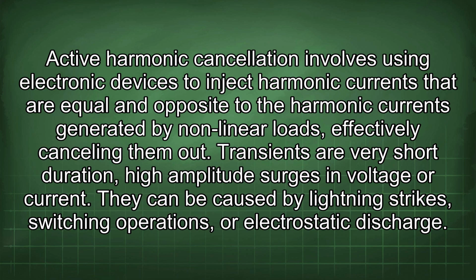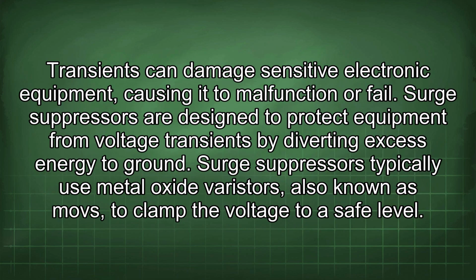Transients are very short duration, high amplitude surges in voltage or current. They can be caused by lightning strikes, switching operations, or electrostatic discharge. Transients can damage sensitive electronic equipment, causing it to malfunction or fail. Surge suppressors are designed to protect equipment from voltage transients by diverting excess energy to ground. Surge suppressors typically use metal oxide varistors, also known as MOVs, to clamp the voltage to a safe level.